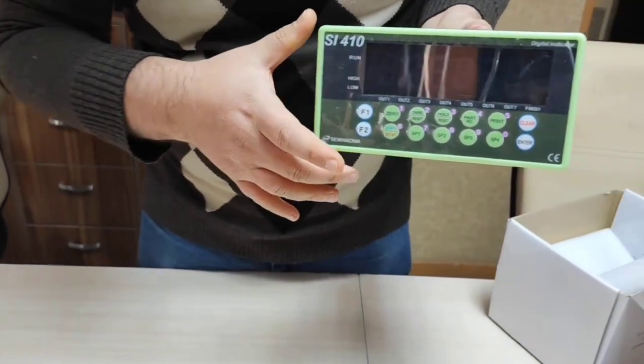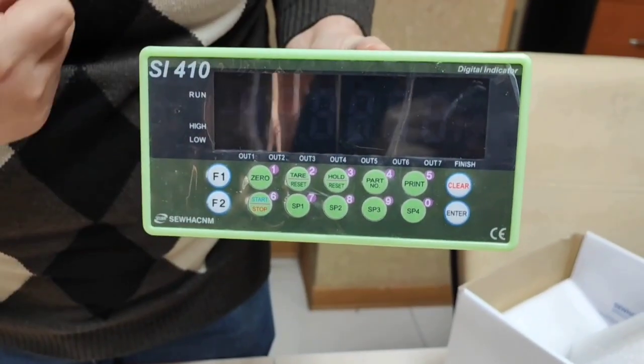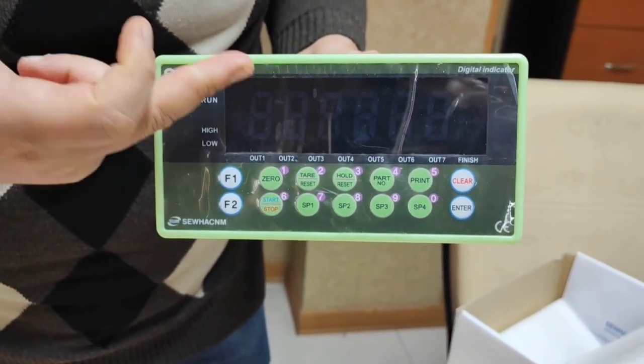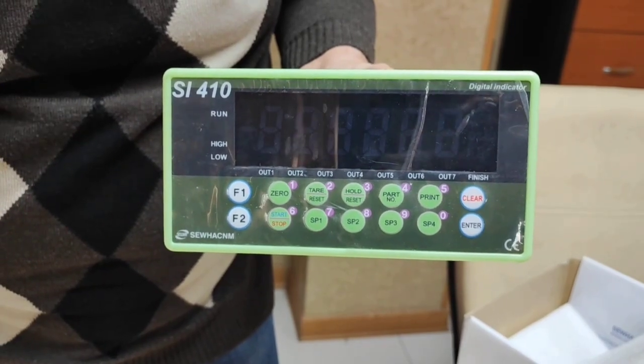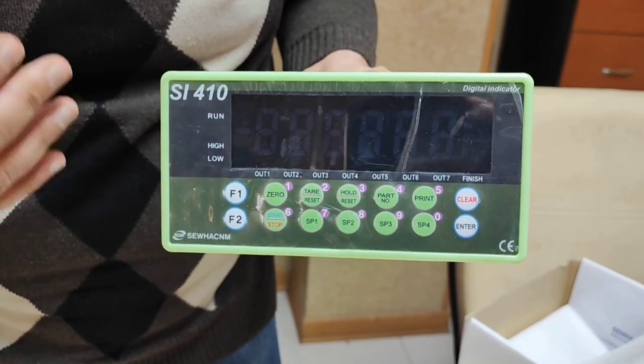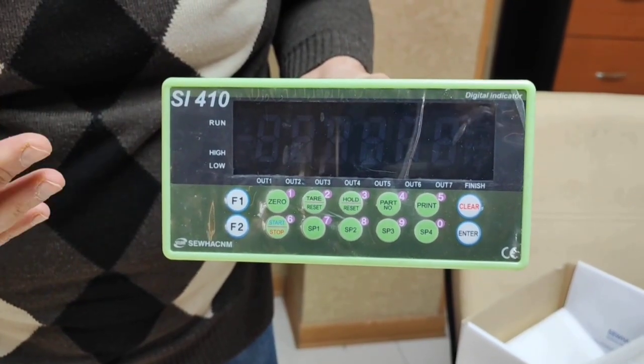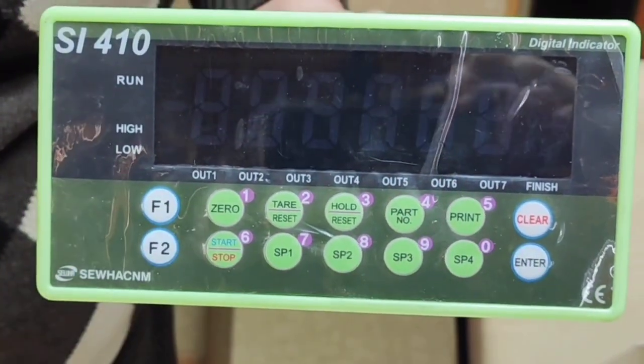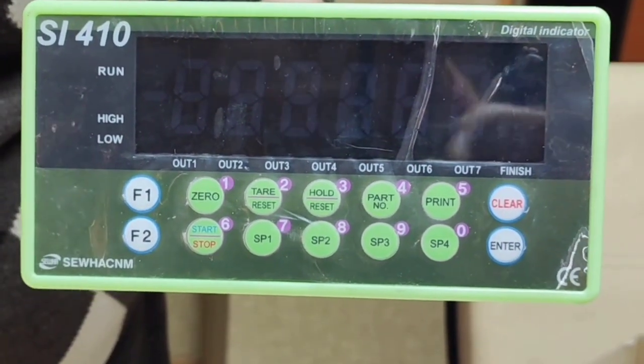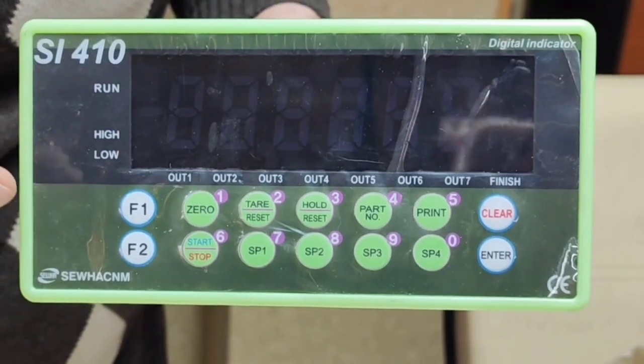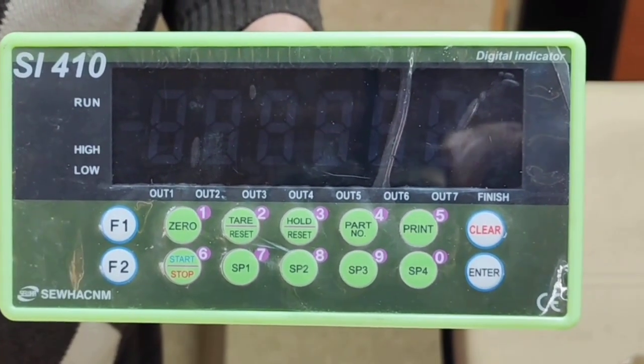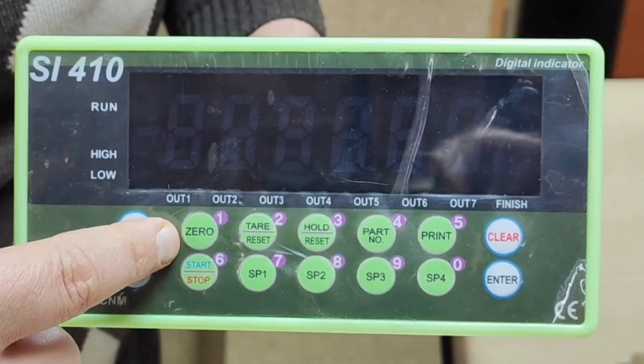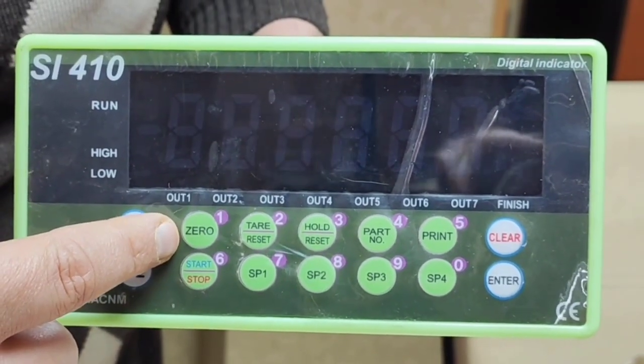So this is the integrated digital display screen area of this particular device, where you can clearly observe the precise weight measurements. Let me explain that this device is both a weight indicator and a weight controller. In other words, besides showing us the weight, it can also control it for us. So we use this device as our controller. Now here we have a number of buttons. The F1 and F2 buttons can be used for calibration as well as for configuring the device. Here we have a 0 button, which we can use to reset the scale to 0.